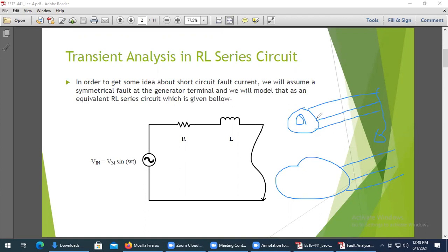You do not need to analyze the separate phases, especially the currents and voltages of the different phases separately. You can analyze only one phase, find the fault current or fault voltage there, and eventually get a clear idea about what's happening to the other phases, because the other phases will have the same nature.